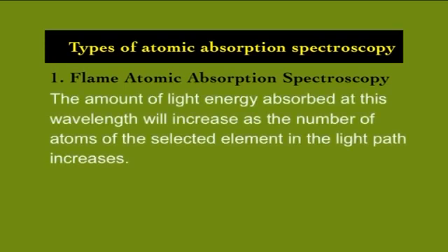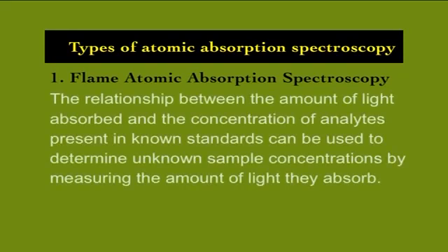The amount of light energy absorbed at this wavelength will increase as the number of atoms of the selected element in the light path increases. The relationship between the amount of light absorbed and the concentration of analytes present in known standards can be used to determine unknown sample concentrations by measuring the amount of light they absorb.